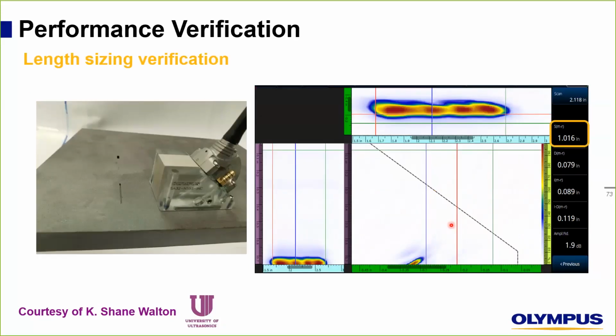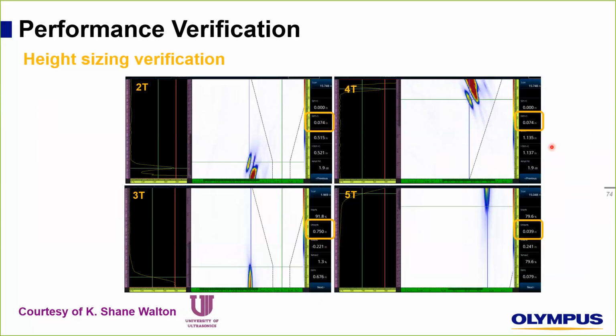The next performance verification is the length sizing verification. It's used on the notch here. Of course, if you have just one notch, you just have to flip your cal block. And here, the measure was almost 1 inch, and it corresponds to the length of the notch provided by Shane. The height sizing is used also on the same notch.